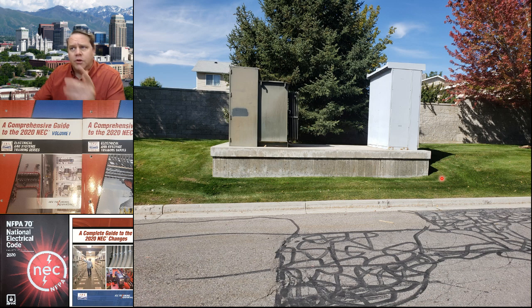Probably, but you could debate that. The first issue that comes to mind is the maximum height of the circuit breaker, which is 6'7". So we'd have to make sure we satisfy that. But as far as the working space goes, it does not have to be level or flat. There have been proposals to require that, but they were rejected because it would be impossible to do.